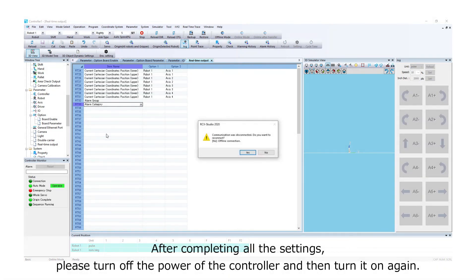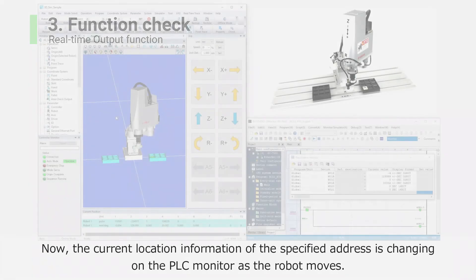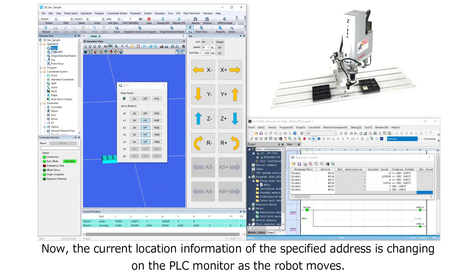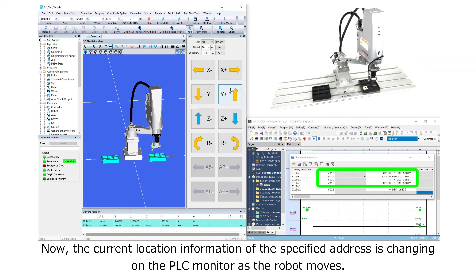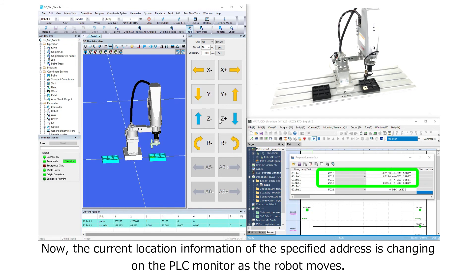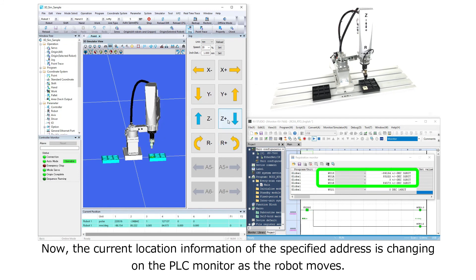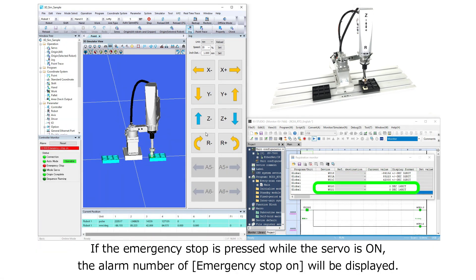After completing all the settings, please turn off the power of the controller and then turn it on again. As an example, we set to output the current position of the 4-axis robot and alarm information. The current location information of the specified address is now changing on the PLC monitor as the robot moves. If the emergency stop is pressed while the servo is on, the alarm number of the emergency will be displayed.